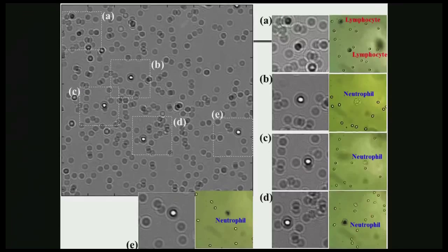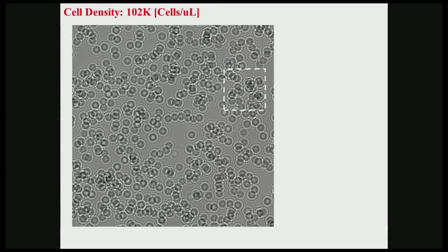So if you look at, for example, whole blood, you'll be mostly seeing these shadows of red blood cells, and every now and then you would see a white blood cell. It could work like a cytometer, a blood analyzer, based on essentially computer vision and based on these shadows or library of shadows. But it's more powerful than that because it can also do reconstruction, because these are not dummy shadows.